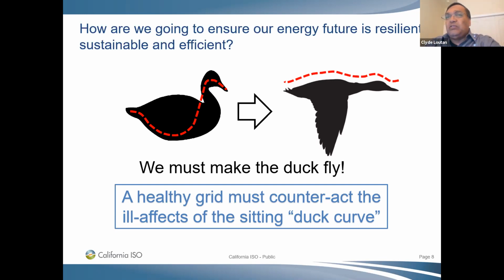So when we integrate renewables, you got to make sure that you can meet those standards in real time. So you got to set the system up ahead of time. So if it means curtailing renewables, you're going to have to, because you do not want to operate a system where you're going to ship some of your problems off to a neighboring system. So it's pretty strict standards that we got to follow. And with those strict standards, we may have to curtail renewables in order to meet or comply with those standards.